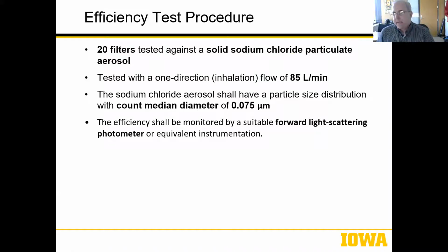Okay, so now how do they test these filters? Again, Sami and his group there, Dr. Ranganasamy at NIOSH, know this very well. They helped develop the procedure, and they start with sodium chloride, table salt. You make a solution of it, so now it's dissolved in there, and then you nebulize it into droplets.